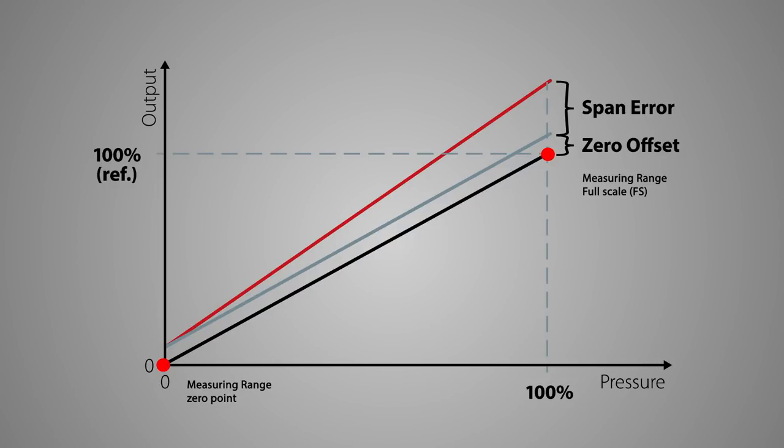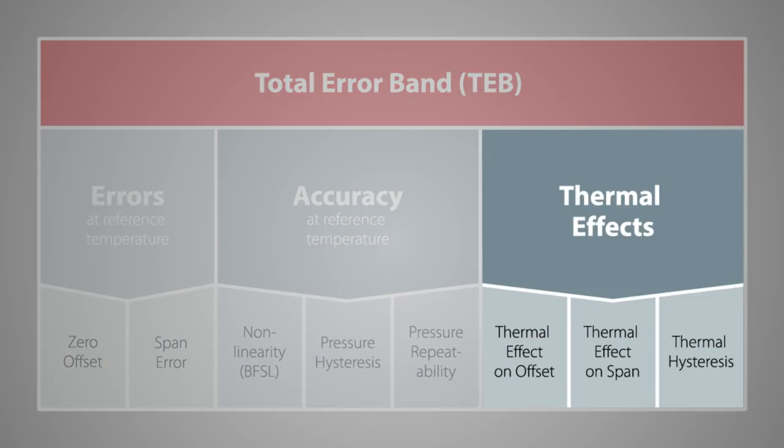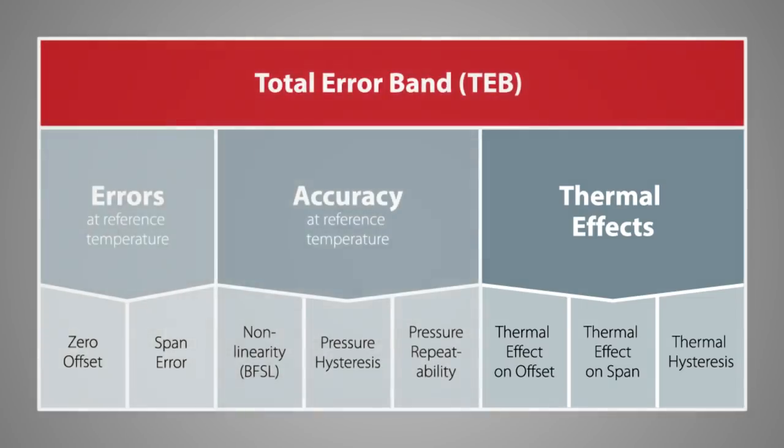The span error describes the error of the output signal at the full scale value minus the zero offset error of the measuring range. Moving to the thermal effects, let's look at what can influence your measurement and cause deviations. The thermal effects are mainly caused by the temperature-dependent physical characteristics of the mechanical and electrical components used to build electronic pressure transmitters. For instance, the electrical resistance of metal increases with the rise of temperature, where the piezoresistive effect of the semiconductors decreases.